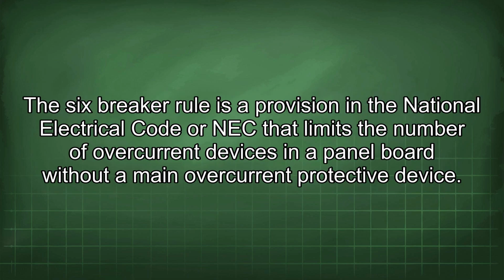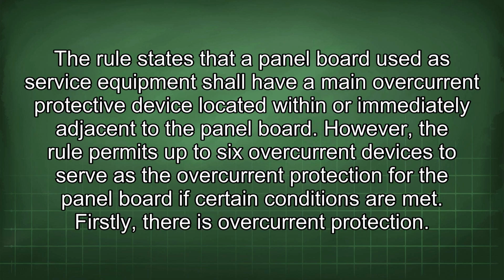The 6-breaker rule is a provision in the National Electrical Code, or NEC, that limits the number of overcurrent devices in a panel board without a main overcurrent protective device. The rule states that a panel board used as service equipment shall have a main overcurrent protective device located within or immediately adjacent to the panel board. However, the rule permits up to 6 overcurrent devices to serve as the overcurrent protection for the panel board if certain conditions are met. Firstly, there is overcurrent protection.